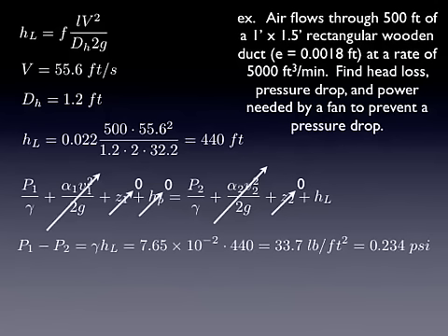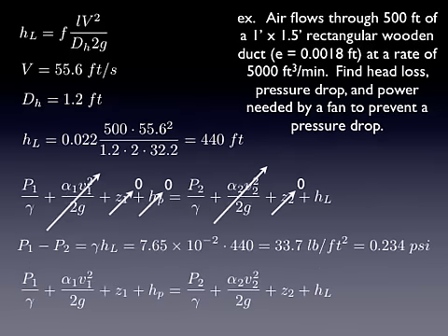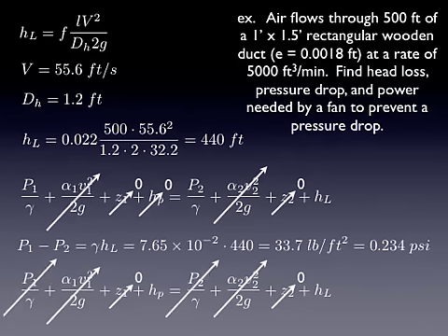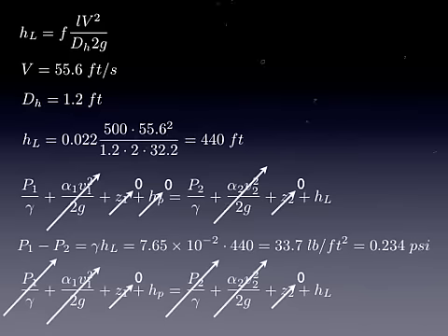And then finally, if we're going to use a fan here to eliminate that pressure drop, let's go back to the energy equation. Same assumptions. The velocities are the same, so they cancel out. The elevations are the same, or they're set to zero, so they drop out. Now we're going to have a pump head here because we have a fan, but we're doing it such that the pressure difference is zero. So these pressures are going to cancel out. So all we're left with is the pump head equals the head loss.